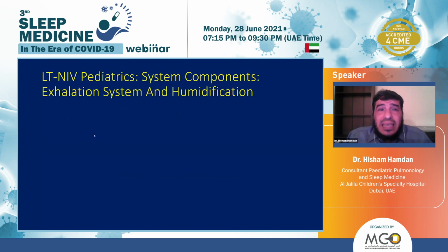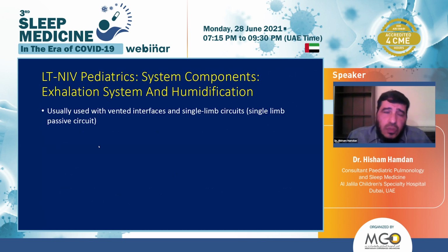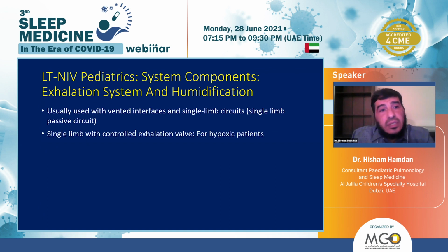System components: the exhalation system is somewhat confusing for some. The exhalation component is, how does the exhalation happen? Usually, the most common type is what's called a single limb passive circuit. In this case, inhalation comes from the ventilator. Exhalation is through vents or openings in the mask itself. So it's a passive process. This offers the best synchronization.